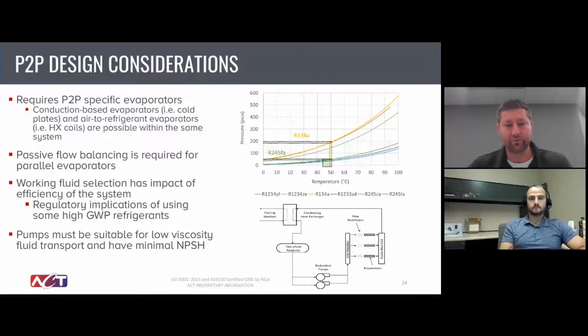And then we didn't talk too much about component selection, but pumps are obviously one of the more critical design elements. We are selecting those for their ability to handle low viscosity fluids, as well as operate with minimal net positive suction head. We need to create a pump that meets the pumped two-phase requirements, and then we'll select based on availability and cost. But most of the time we are designing with off-the-shelf pumps that are readily available.